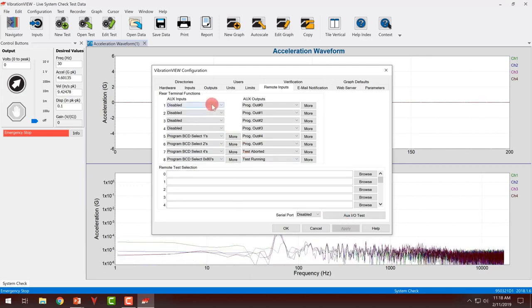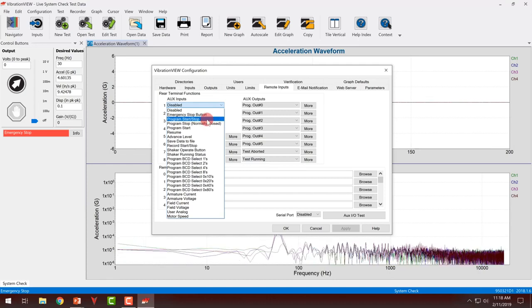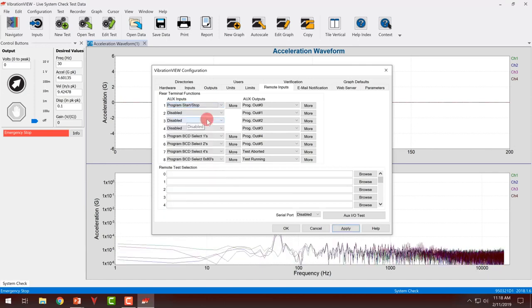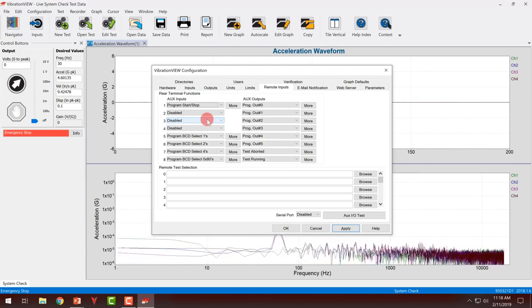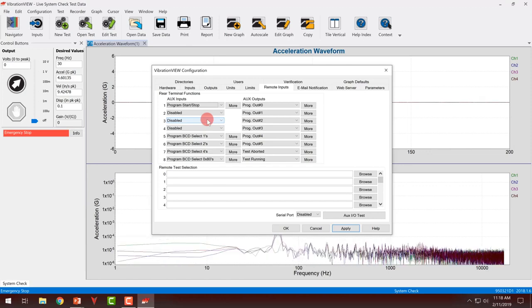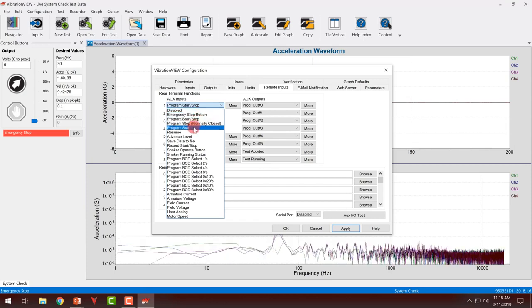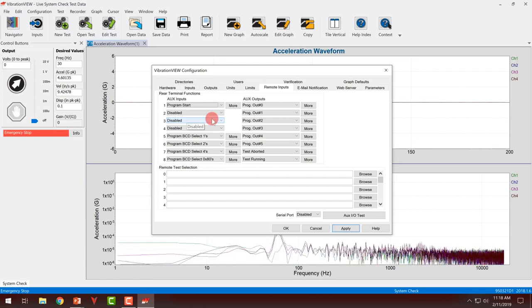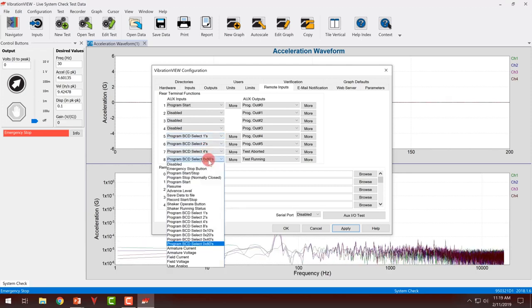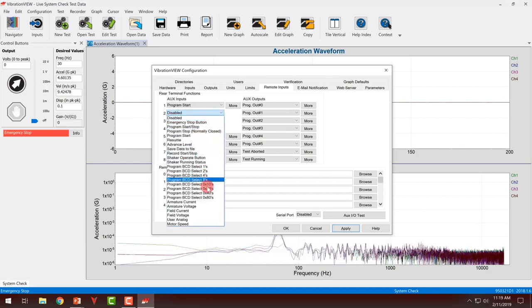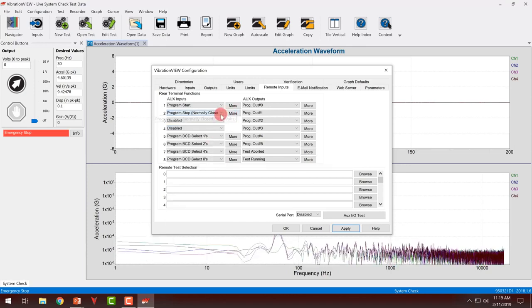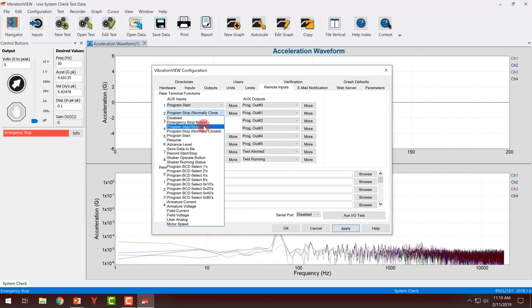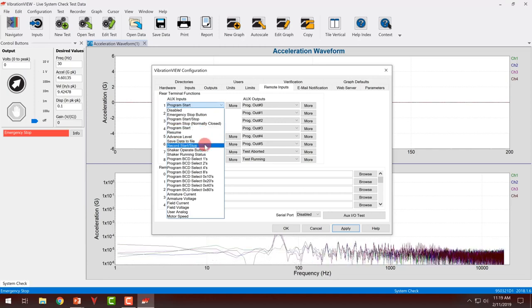Then I have to select a program start, program stop, or program start stop. Program start stop means that when I want to start a test, whatever that start signal is has to be held. If I release that start signal the test will stop. I could also do program start, which means I just have to momentarily enable that input. In this case we'll use program start stop in the first position here.